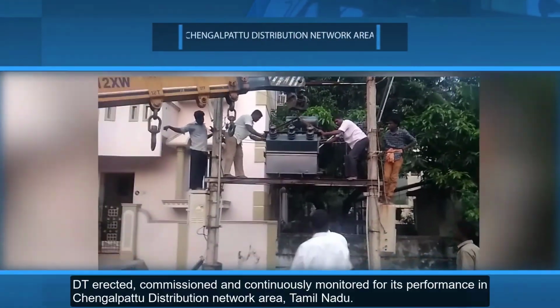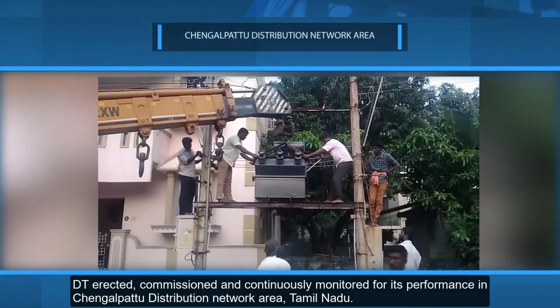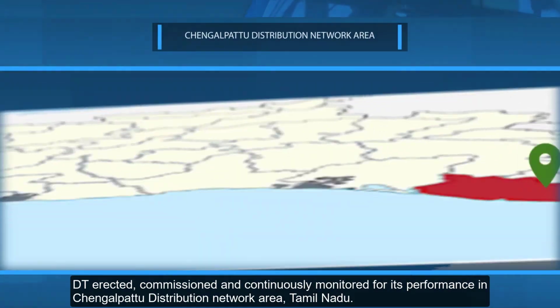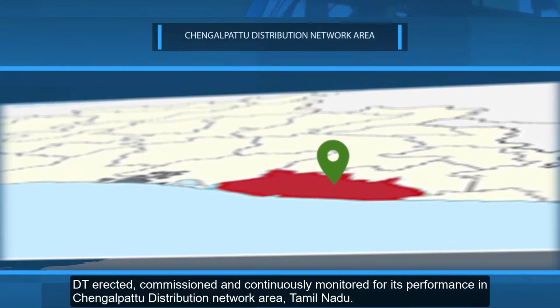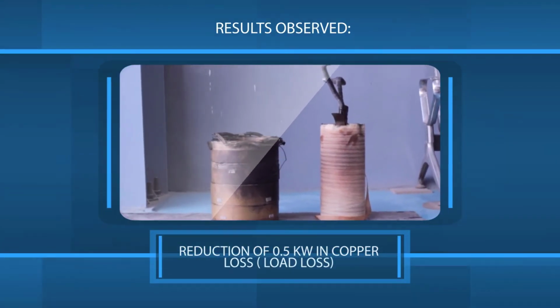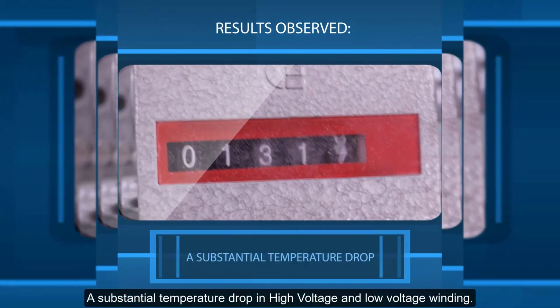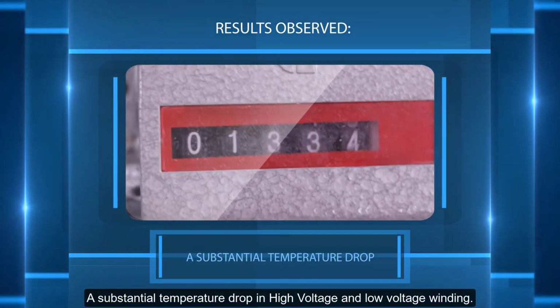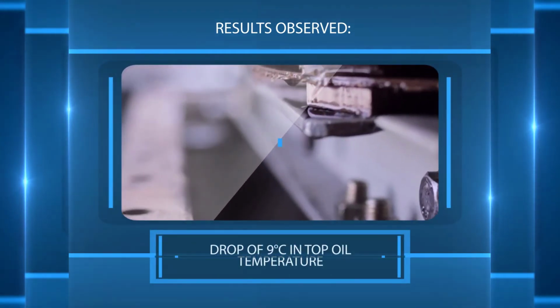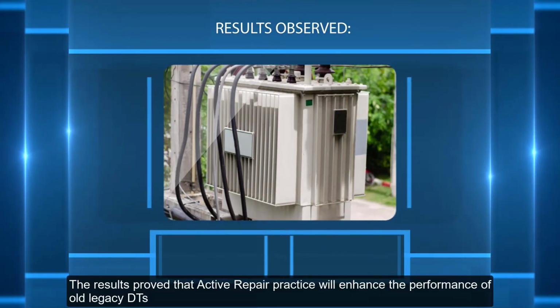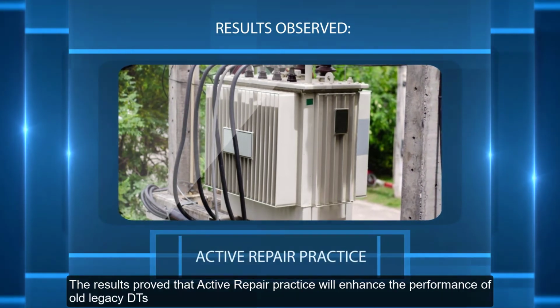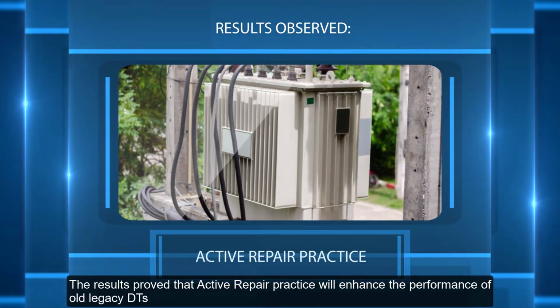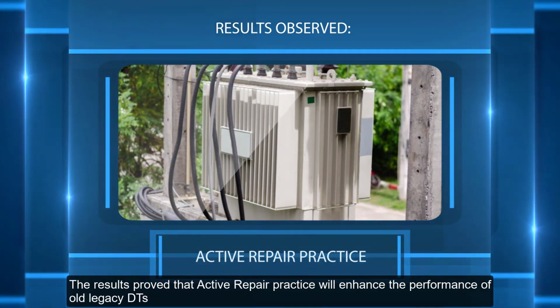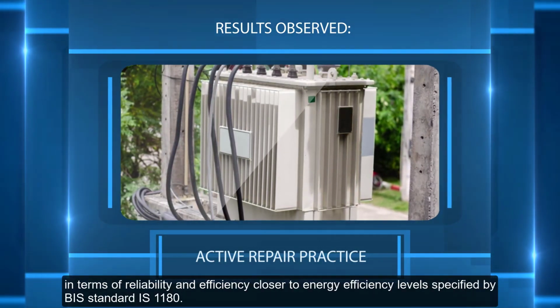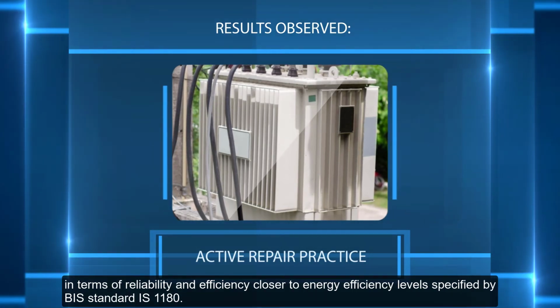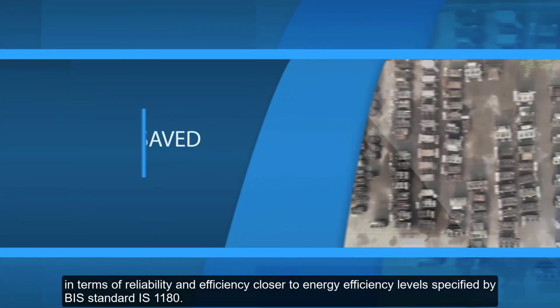After a detailed study, the DT was erected, commissioned, and continuously monitored for its performance in the Chengalpattu Distribution Network area. The results observed were reduction in copper loss, a substantial temperature drop in high voltage and low voltage winding, and a drop in top oil temperature. The results proved that the proposed active repair practice will enhance the performance of old legacy DTs both in terms of reliability and efficiency, closer to energy efficiency levels specified by BIS standard IS 1180.